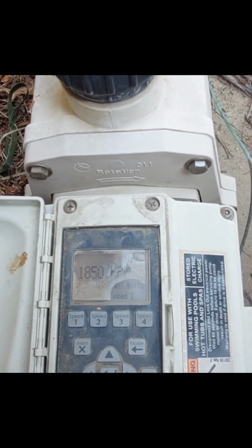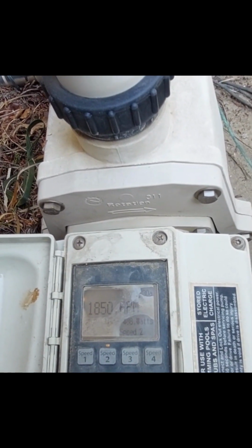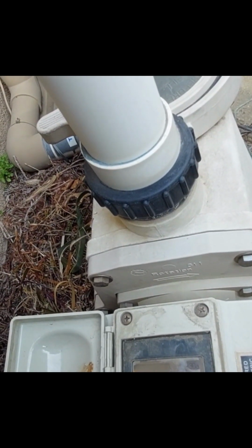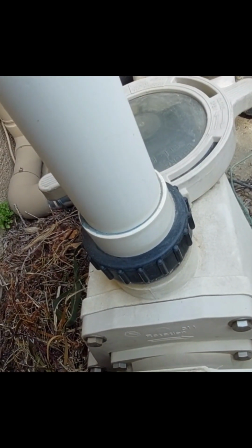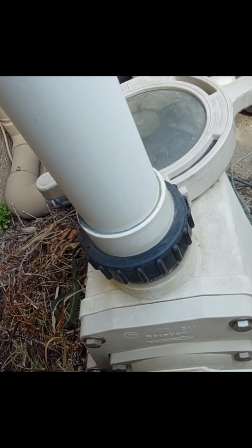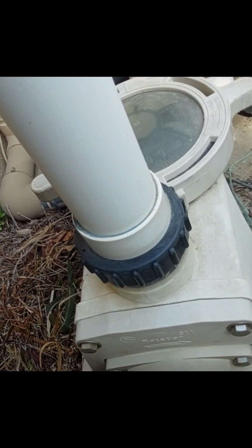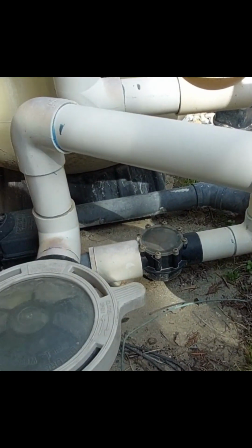I don't really like this older pump. You can't adjust the priming speed. It jumps up to 3450, 3440, which I don't like because if you have a system that operates with high pressure anyway, then there's a chance of running a 3 horsepower pump at full out could crack the filter, but they have a 600-pound tagless sand filter. It could take that kind of pressure, but some filters can't.